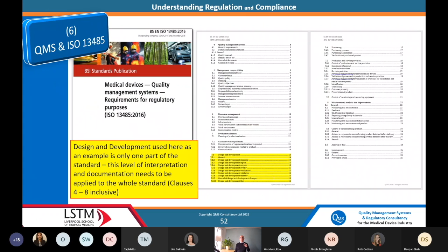Now, what I've just described there is section 7.3 of the standard, and as you can see, it's quite a small section compared to everything that you need to do. The standard says all the way through it, the organisation shall document procedures for, and the word shall means must, so you must document procedures, and every number on this screen now is a clause that says you must create a document. But don't worry, this is at launch. When you're at early stage development, you only need a handful of procedures to support what you're doing, and build in more procedures as you go along.